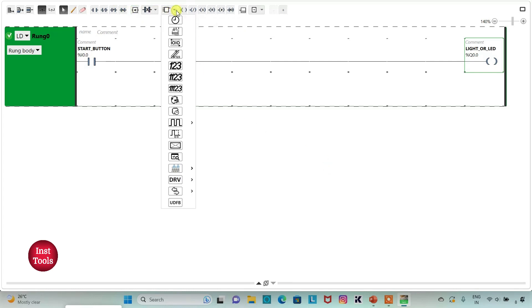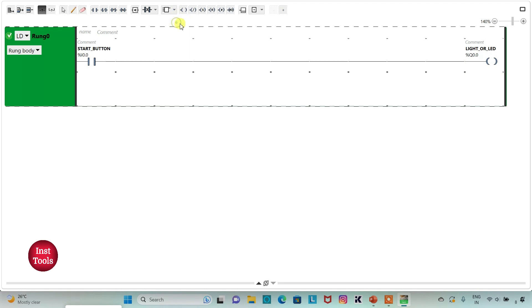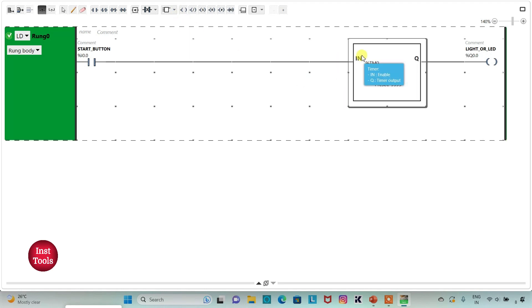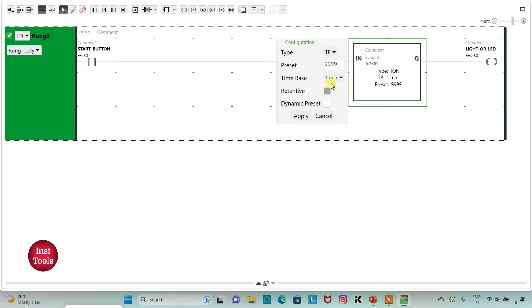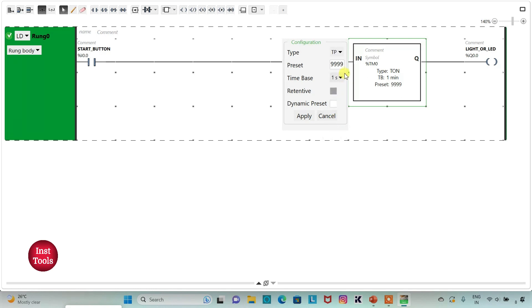Then I will insert a functional block timer and change the type of this timer to TP, which is Time Pulse. I will change the time base to one second and the preset value to 2, then click Apply.